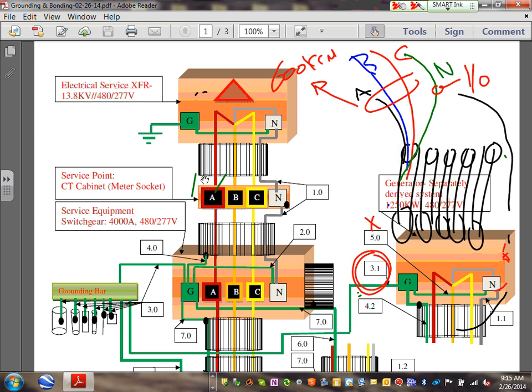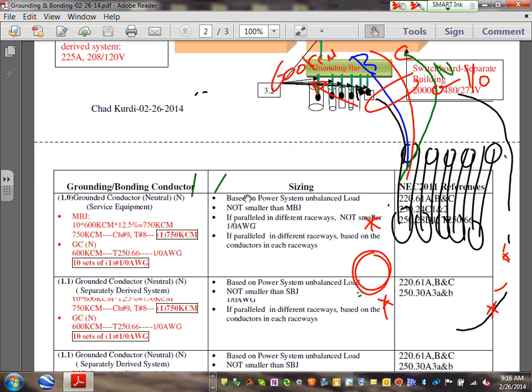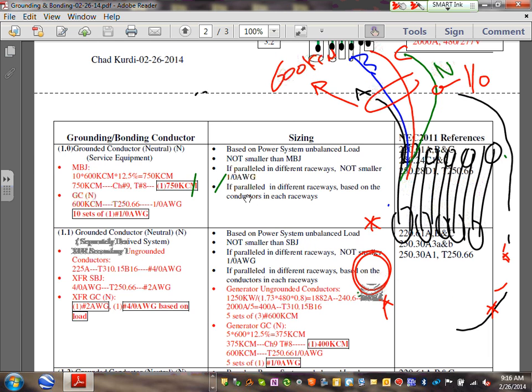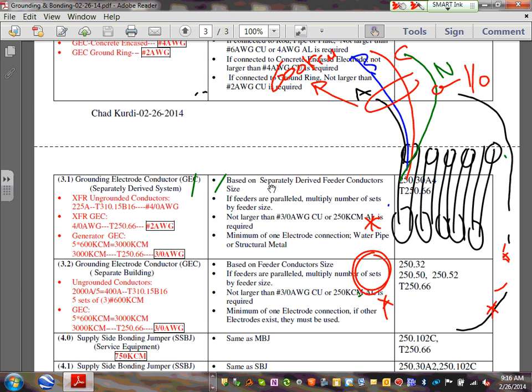So we size the system bonding jumper, gentlemen. We size that neutral, and we size the supply side bonding jumper. Last thing is 3.1. That's a wire that goes from the generator all the way to the ground bar, or typically to the ground bar attached to the wall in the electrical room, where you bring one from the transformer, one from the switchgear, one from all the separately derived systems, all come to that bar, one connection. Okay, let's go size that baby, 3.1, shall we? So let's go all the way to 3.1, gentlemen, 3.1. Here you go, right here.